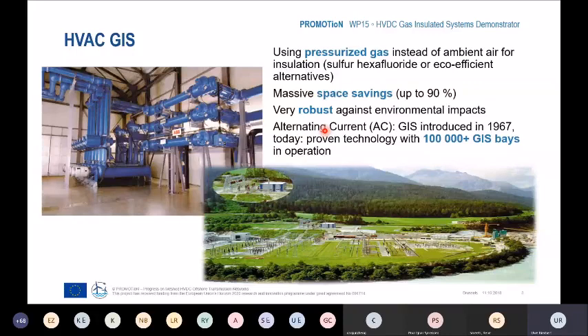gas insulated switchgear. The technology of gas insulated switchgear is not really new. It is well proven for more than 50 years. You can see here on the left side a picture of a 550 kV AC GIS, and looking back, we have more than 100,000 GIS bays in operation around the world. The first one was installed in 1967, so more than 50 years ago.